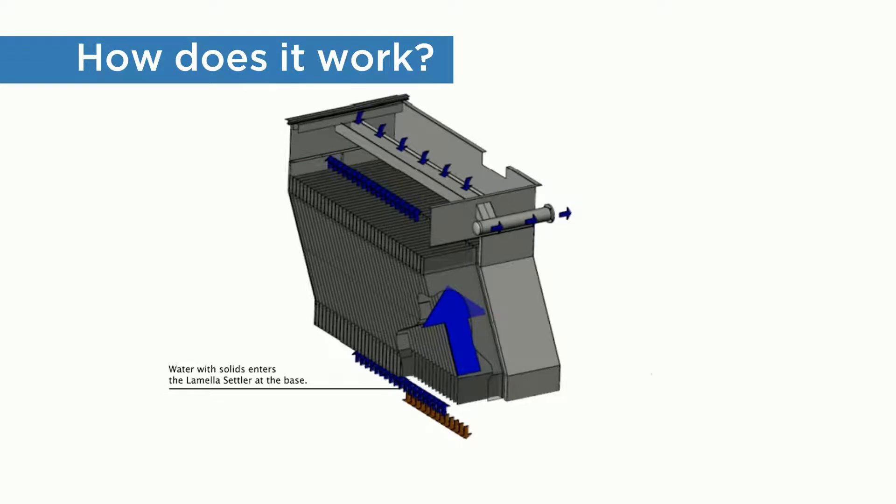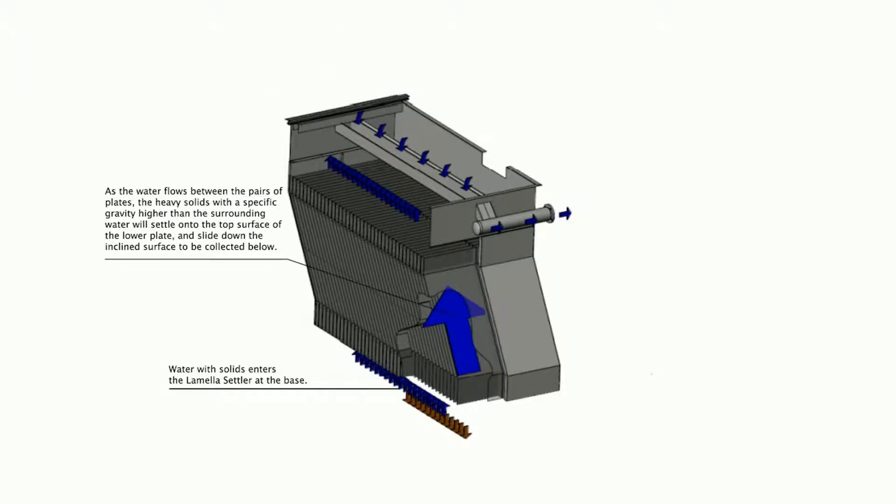The lamella clarifier consists of a series of closely spaced flat plates inclined at an angle. Preconditioned water with entrained solids enters the plate pack and flows between the plates. The path length, plate spacing, and angle of the plate are the usual engineering variables.